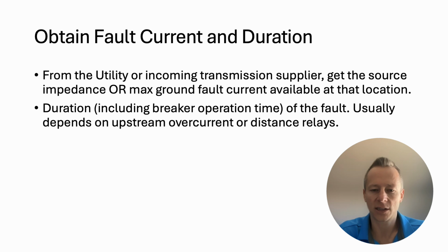And we base our studies off of the max ground fault current on the high side of the station. There's reasons for that we can discuss later, but for now we're going to leave it at you need the fault current and the duration. And the duration can be overcurrent protection depending on the upstream protection and control that's set. So it might be overcurrent. In that case, you need the trip value at the max fault current, and then add in the breaker operation time too. So you might have a 3 to 5 cycle breaker actual operation once it gets the signal from the relay as well.